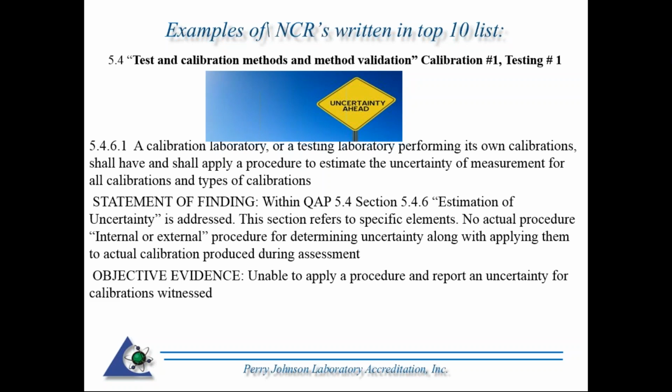So the requirement I'm referring to here is 5.4.6.1. A calibration lab and also a testing lab performing its own calibration shall have and apply a procedure to estimate the uncertainty of measurement for all calibrations and types of calibrations. Hence, pretty straightforward there. You have that word shall. As I've covered in my presentation on internal audits, a shall is a requirement. A should is a recommendation.